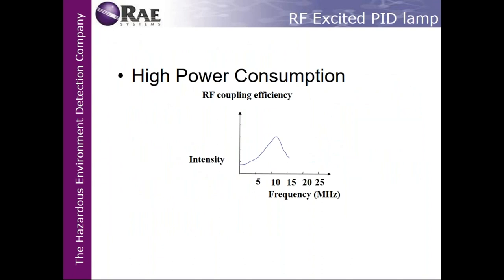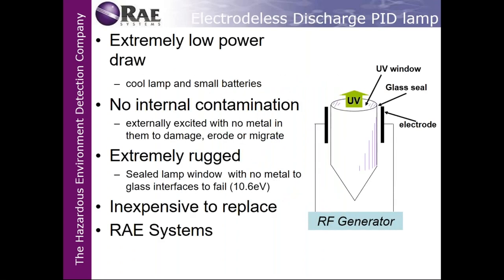Again, here's the high power consumption with a PID lamp. But what happens with the newer design is that it is extremely low in power draw. It is a cool lamp that uses small batteries. There's no internal contamination. It is externally excited, with no metal to damage or erode or migrate. So as you can see by this picture, it's different from the last picture I showed you, where there was a lot of interference with metals or particulates. In this particular example, the lamp is actually cradled inside the monitor, and there's no cross-contamination with metal or any other ways of eroding the lamp.